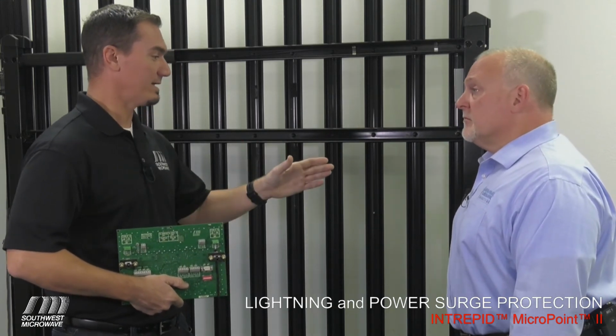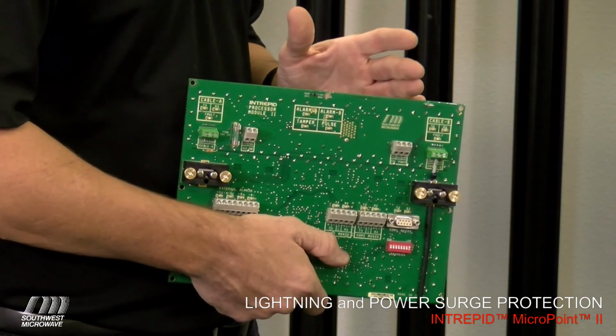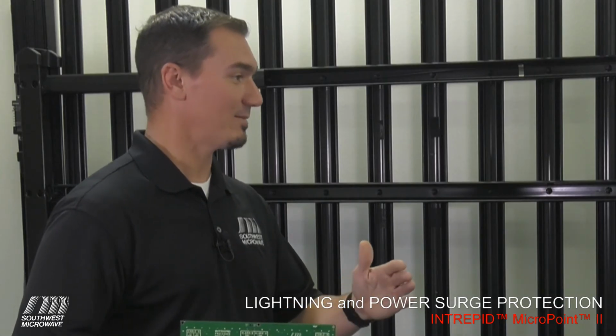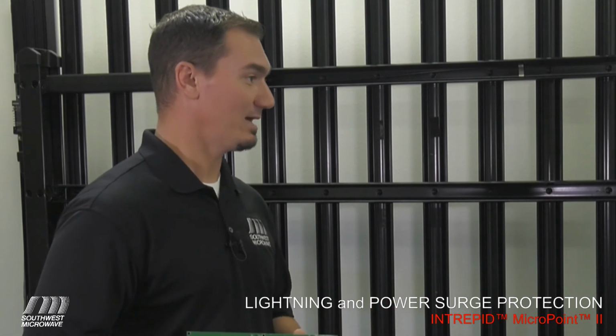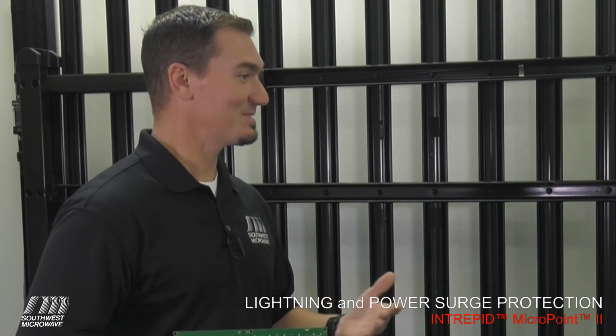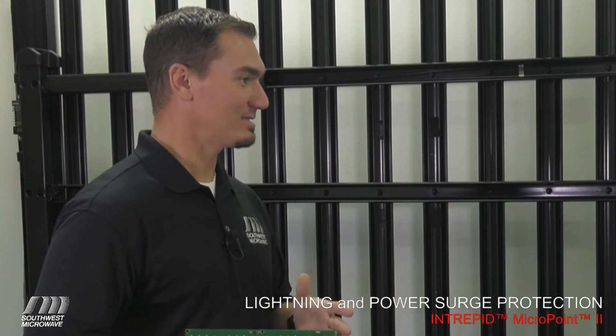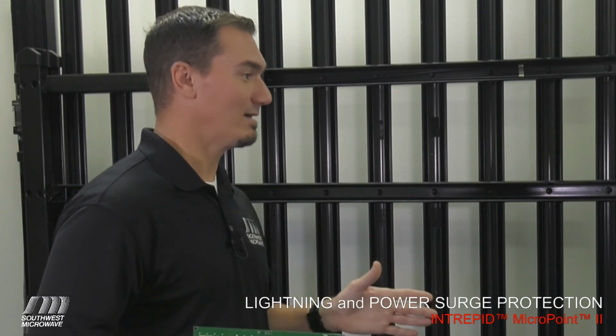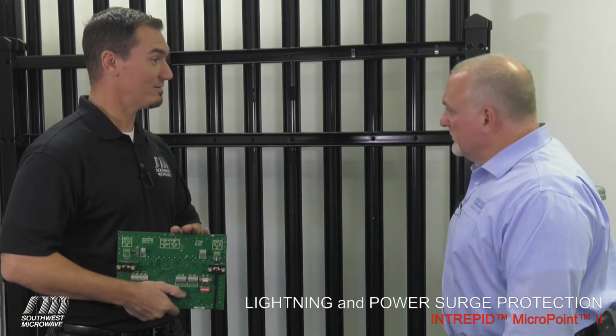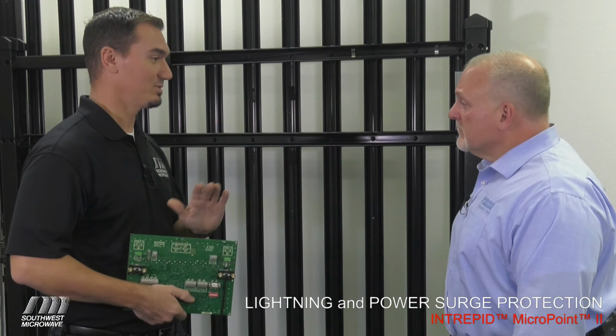One of the ways that we protect is by the floating ground principle. The first processor on the fence, where that JB70 is, is grounded to the JB70, which is then earth grounded. From there, as we move along the sensor cable away from that processor, the floating ground principle applies, and what that does is it takes an alternate ground potential from the fence. Most good fences are grounded. If the fence is grounded appropriately, our floating ground potential electrically isolates all of the electronics and the sensor cable from that ground. And we all know lightning takes the path of least resistance. So if the fence is grounded, and this is on a floating ground with different ground potentials, if lightning strikes nearby or there are ground surges, those will pass right through the fence and completely avoid the cables themselves.